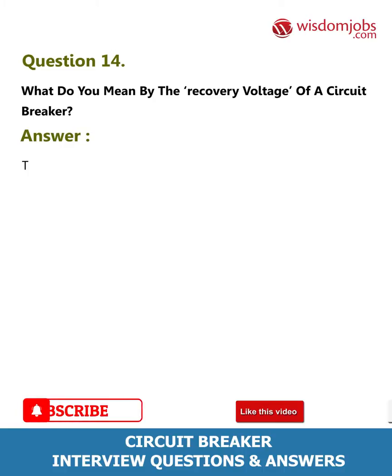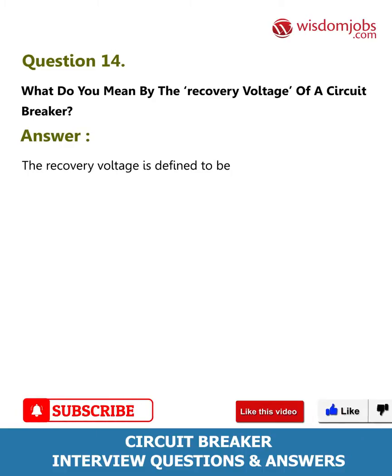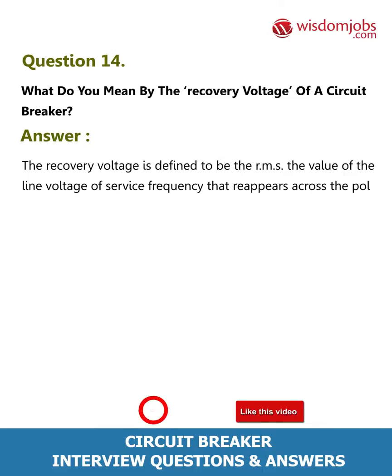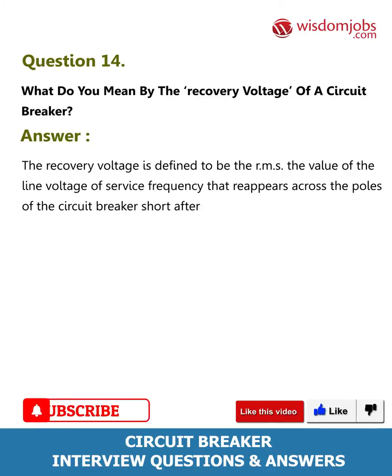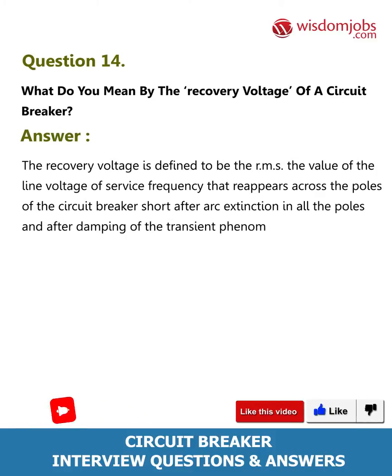Question 14: What do you mean by the recovery voltage of a circuit breaker? Answer: The recovery voltage is defined as the RMS value of the line voltage at service frequency that reappears across the poles of the circuit breaker shortly after arc extinction in all the poles and after damping of the transient phenomena.